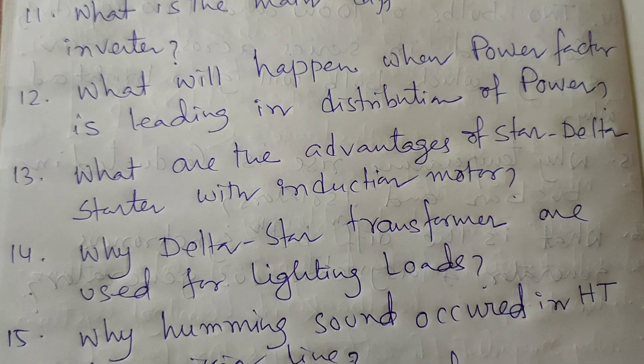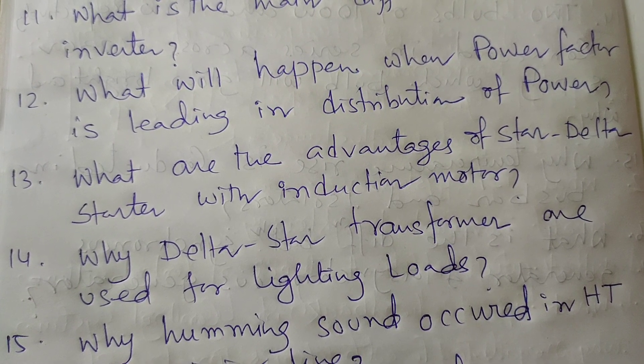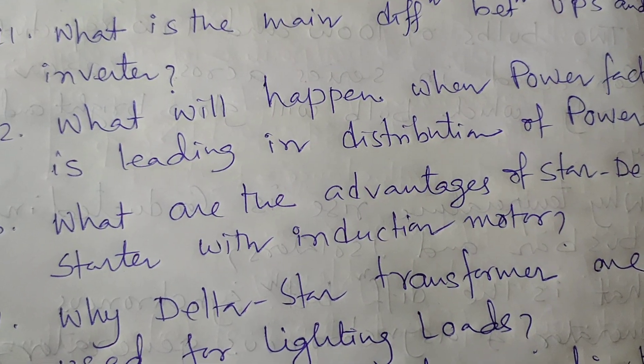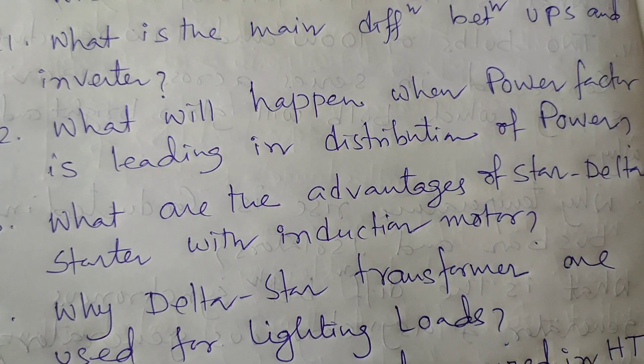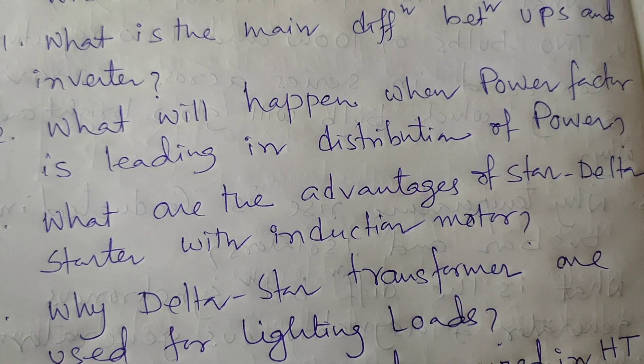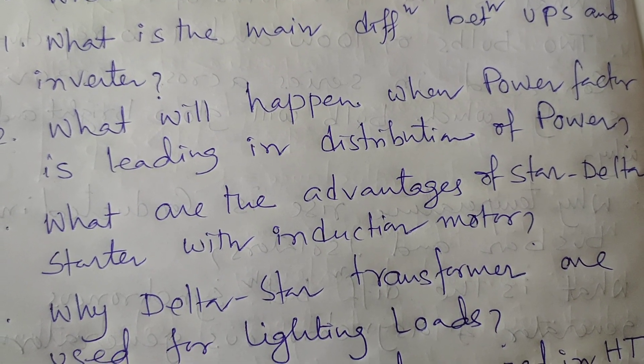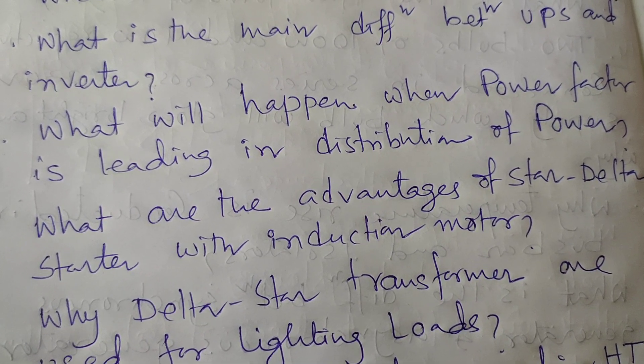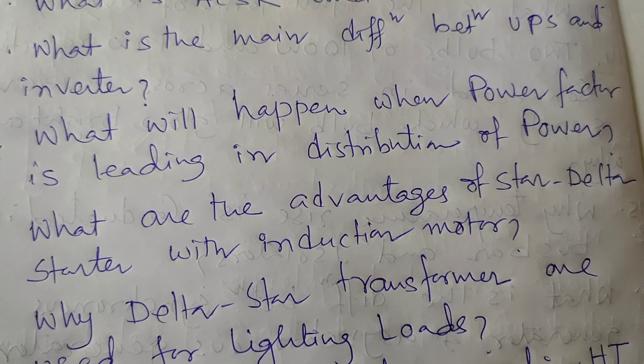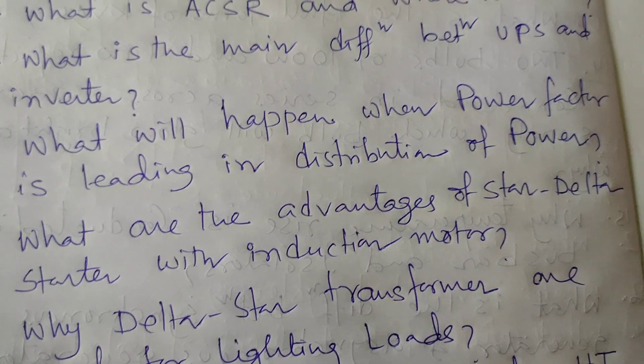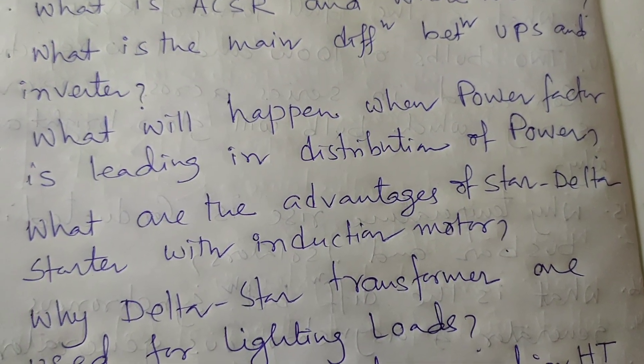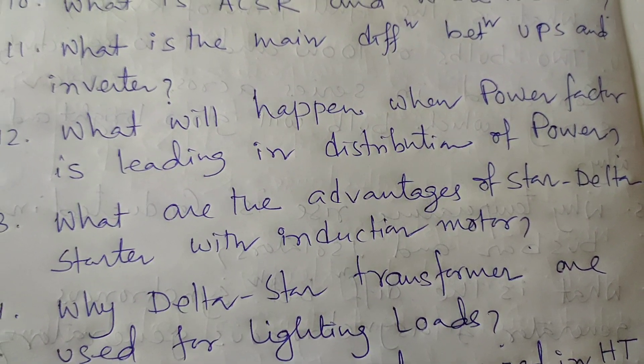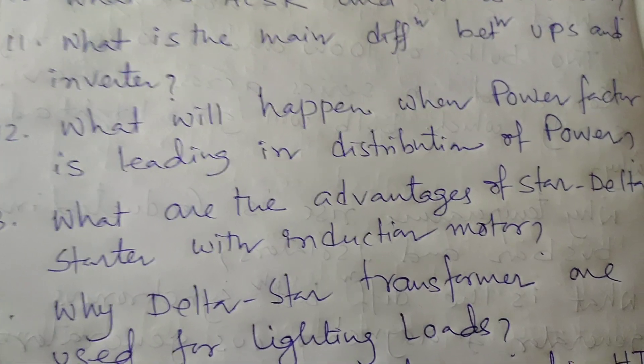Next question: What are the advantages of star-delta starter with induction motor? The main advantage of using star-delta starter is reduction of current during starting of the motor. Starting current is reduced to three to four times less than the current of direct online DOL starter. Hence, the voltage drop during starting is reduced.